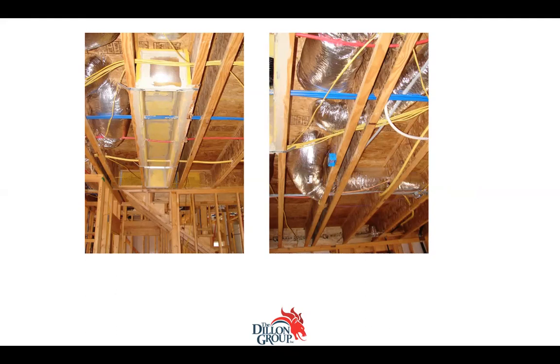Oh yeah, that's allowed by code. Return plenums, you can have gas lines and water lines and plastics and all that stuff in there. That's just so terrible. So I saw a house down in South Padre Island. I got into the attic and looked in the mid-floor and thought, something just seems weird, because I can see where the return duct run is, but I also know there's a toilet over there, and I don't see any plumbing lines right here where I think that toilet should be. So I opened up the return grill and snaked a camera down in there. And right in the return was the plumbing drain for the toilet. It was right in there.